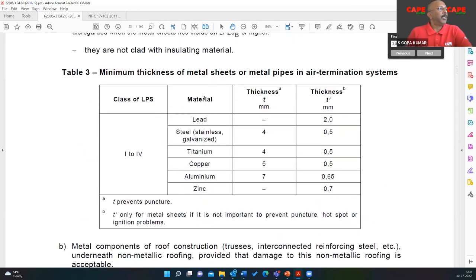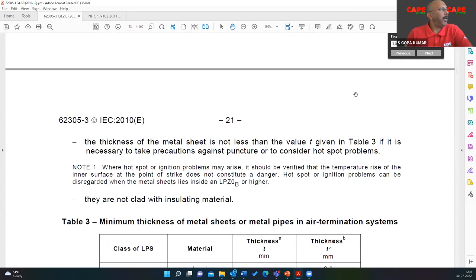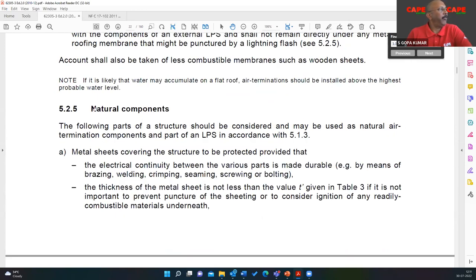It is not on page number 11. Here is the table. So, minimum thickness of metal sheet or metal pipes in air termination system. This part explains the use of natural components. What is a natural component? You have a PEB building with a metal sheet at the top, and that metal sheet is a good conductor. It can be used as an air termination provider.